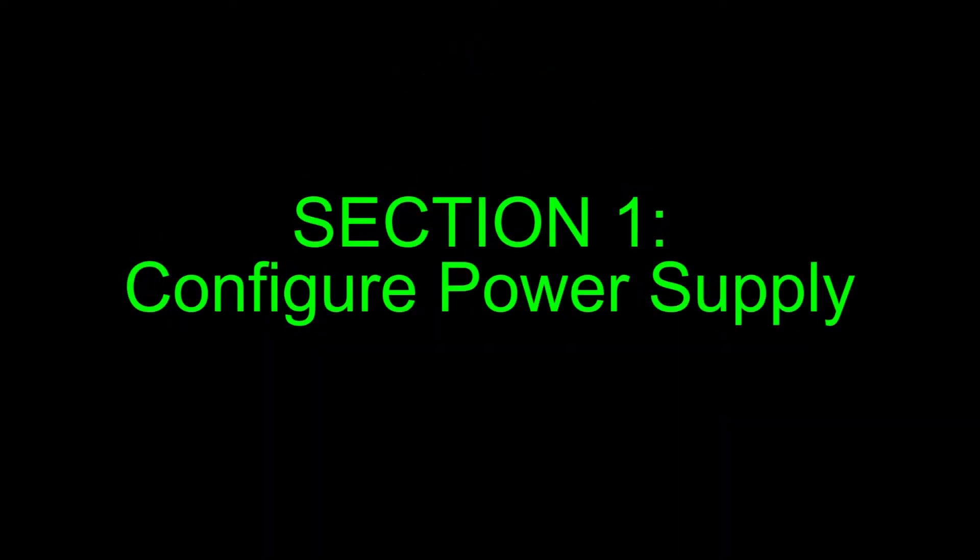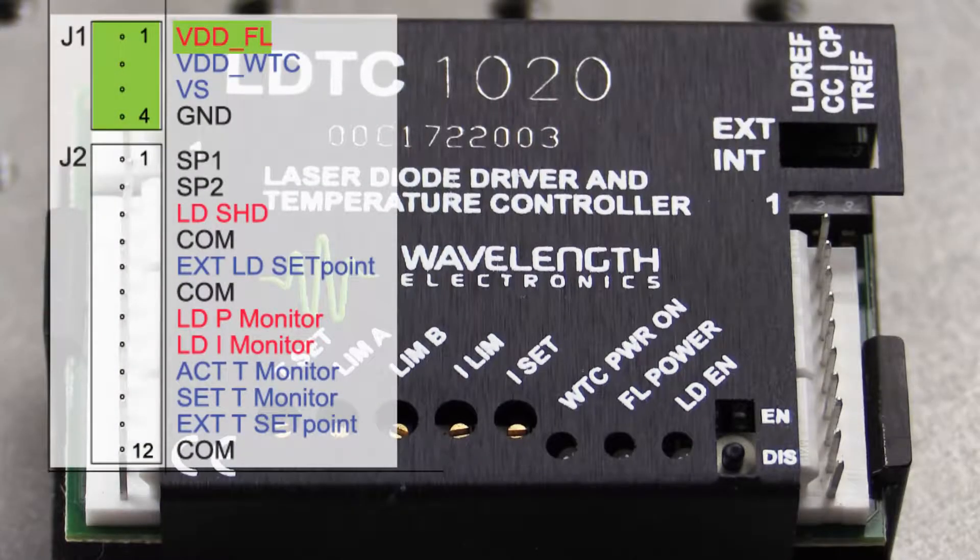There are three power supply connections that must be made. The first is the power supply for the laser driver electronics and the laser diode. The second is the power supply for the temperature controller electronics. And finally, there is a power supply for the thermoelectric.